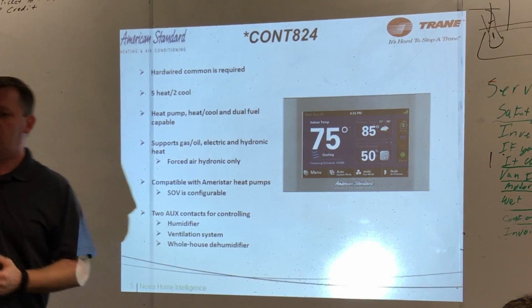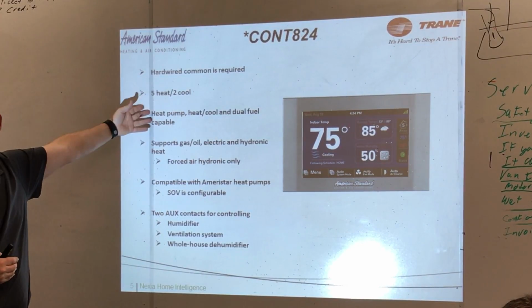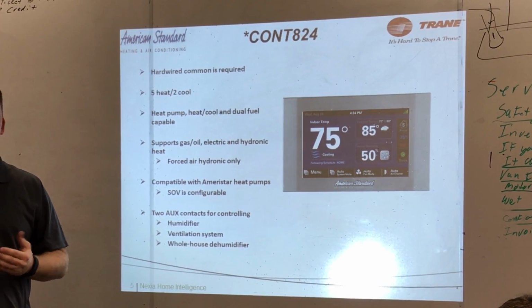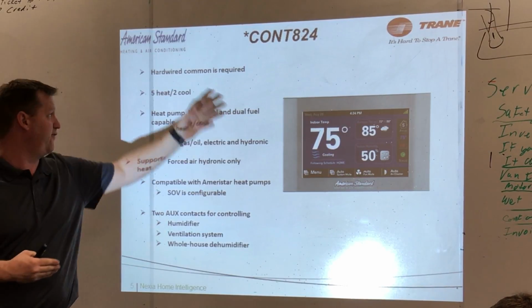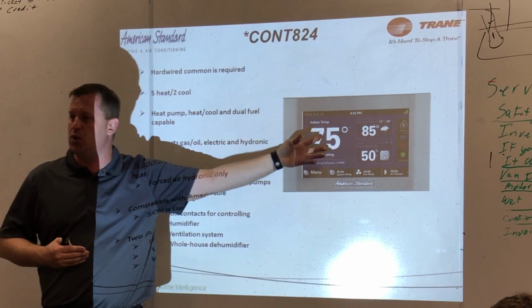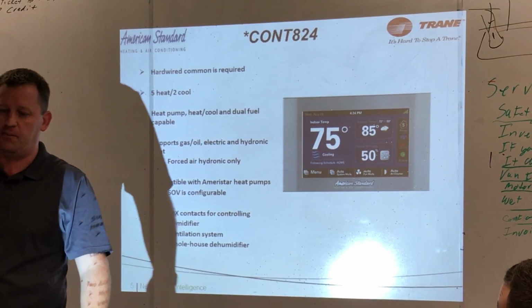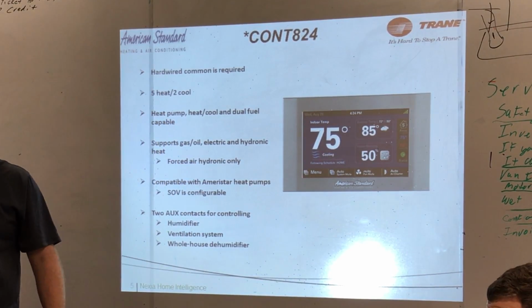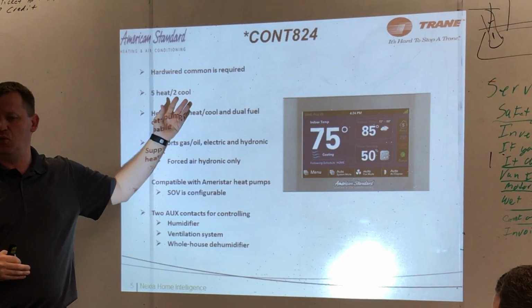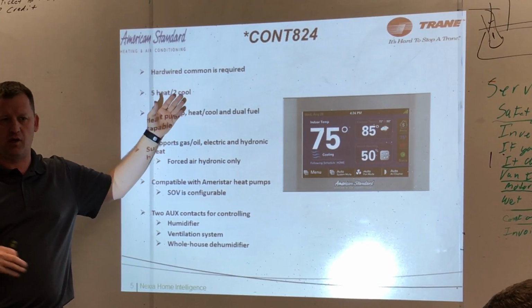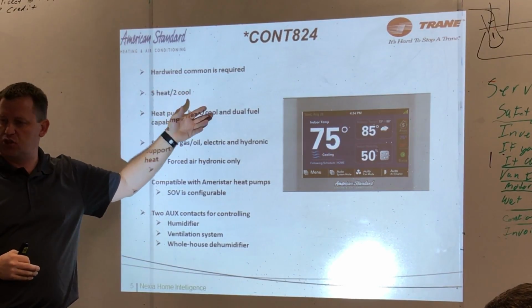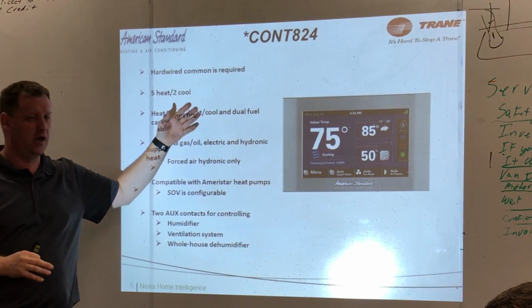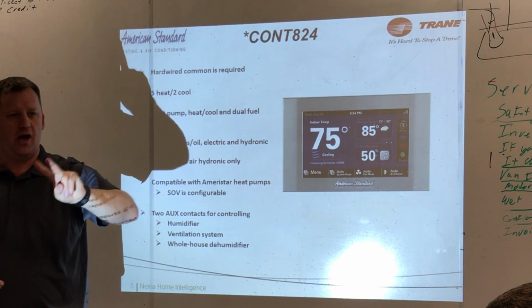When we're setting this up, say someone's getting an 824 stat with a TAM7 and 15K of strip heat, he'd have W1, W2, and W3. With a 2-stage heat pump, that gives us 2 stages of heat and 3 stages of auxiliary.